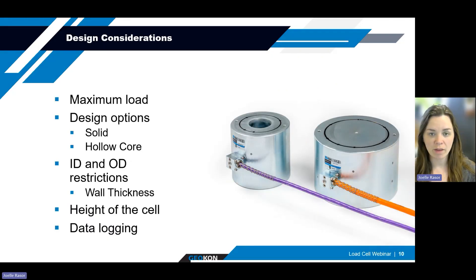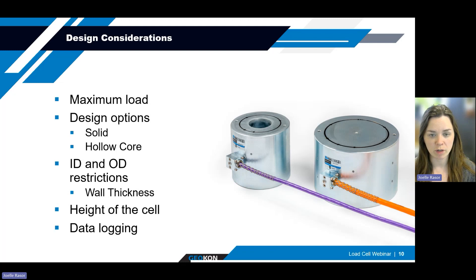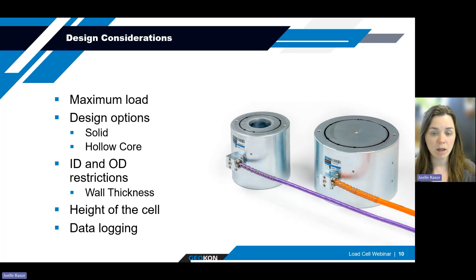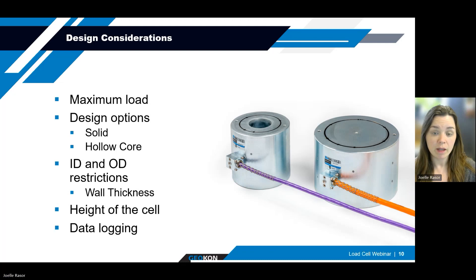Design considerations for either vibrating wire or electrical resistance load cells are fairly simple. First, you'll need to know what your maximum load will be — this information will be important for the manufacturer to determine the appropriate dimensions for your project. It will also need to be determined if any anchoring materials will have to pass through the center of the load cell, such as a tieback, so the necessary inner diameter can be accounted for in the design. If there is some uncertainty, and the center hole is larger, it's possible to provide a bushing to fit the application better.